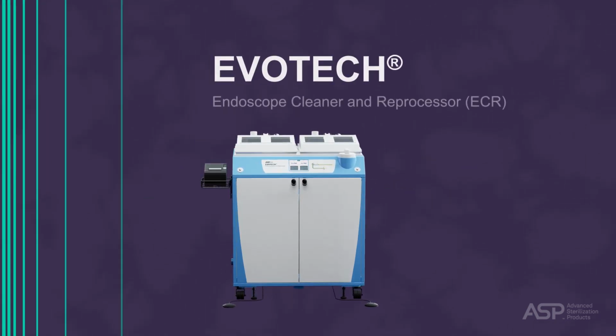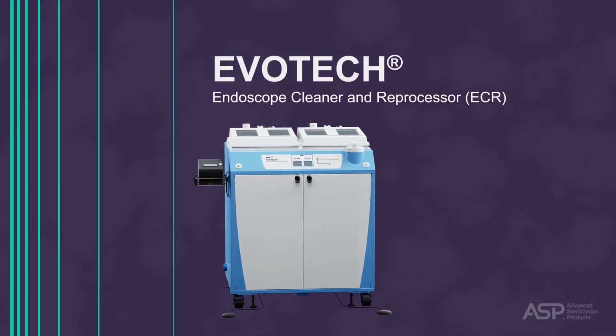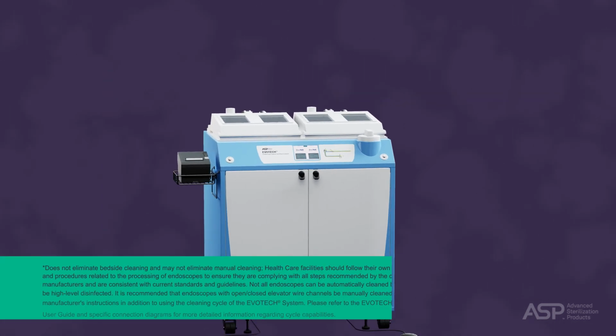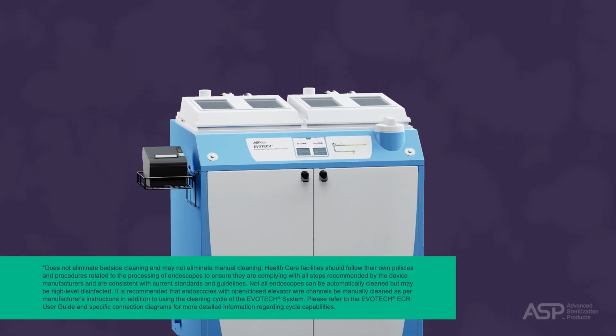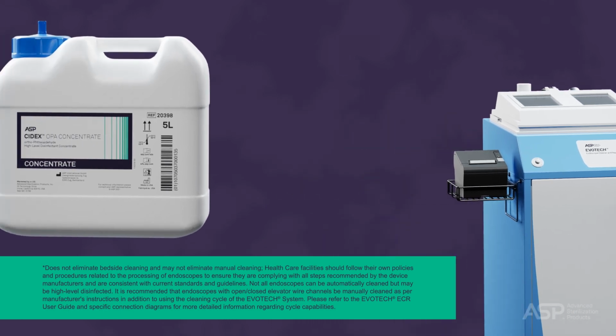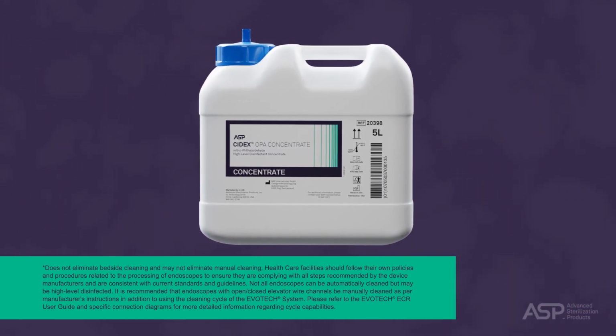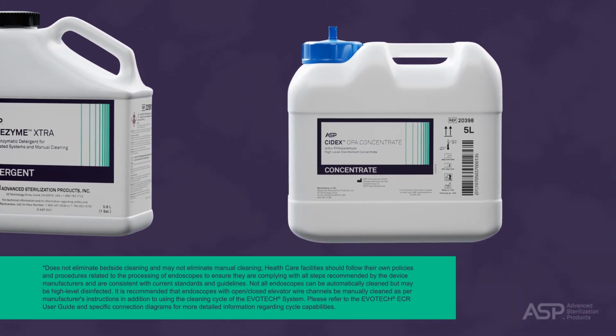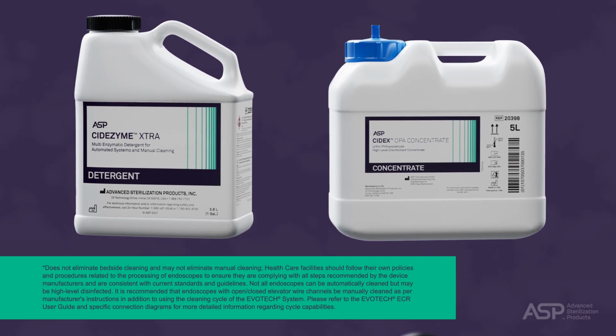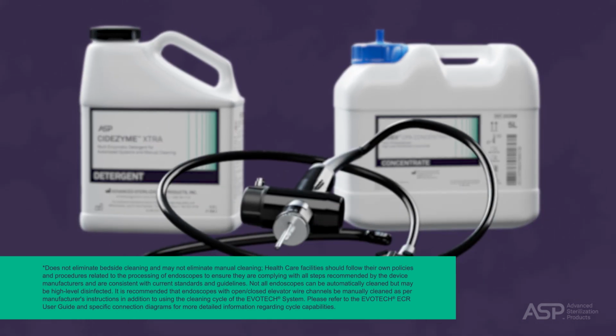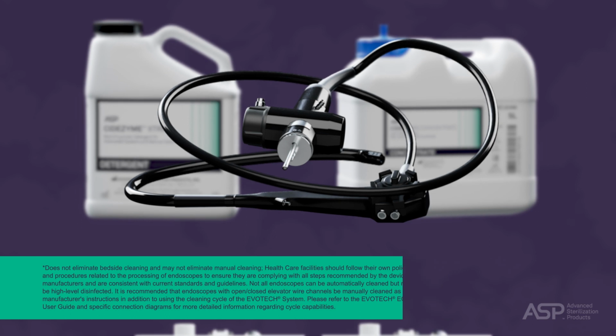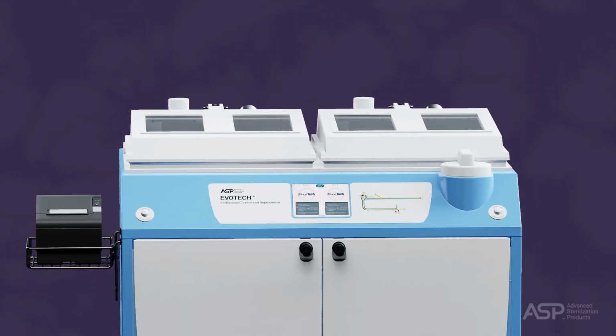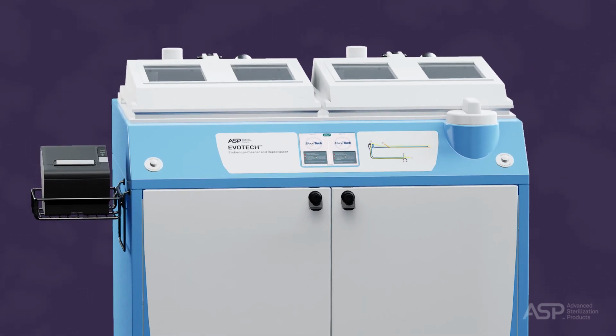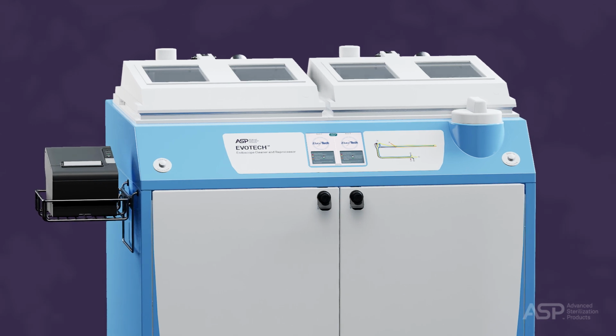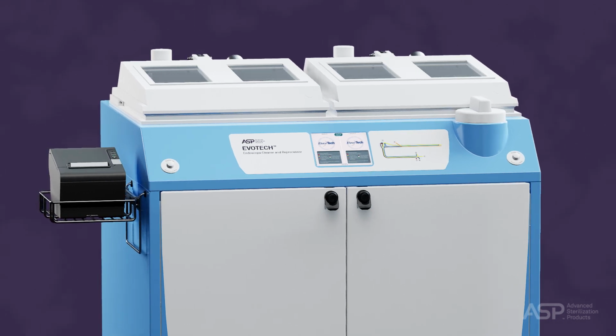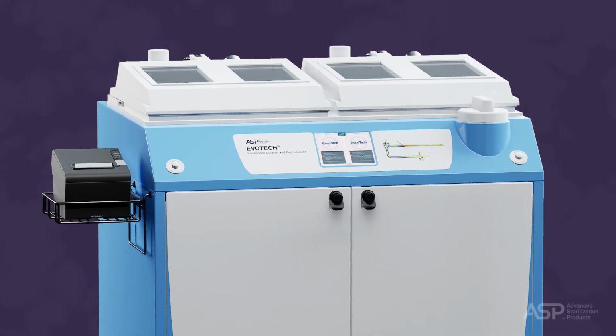The EVOTECH Endoscope Cleaner and Reprocessor (ECR) is a washer and disinfector indicated for use and cleared by the FDA with high-level disinfectant Cidex OPA concentrate solution and Cidezyme Xtra multi-enzymatic detergent to achieve cleaning and high-level disinfection of heat-sensitive semi-critical endoscopes. The EVOTECH ECR is designed to automatically clean and high-level disinfect flexible, submersible video or fiber optic endoscopes.